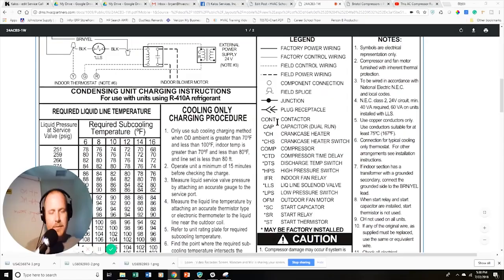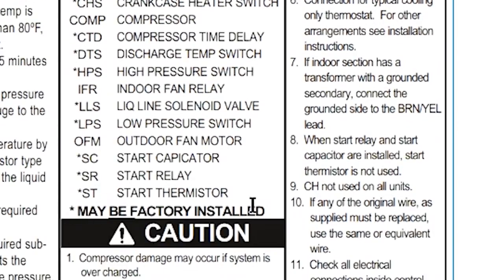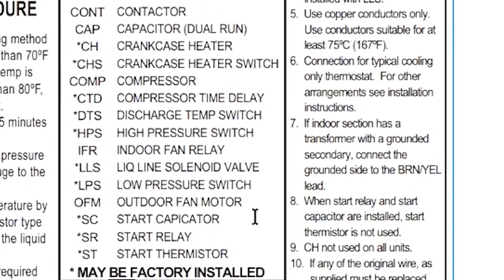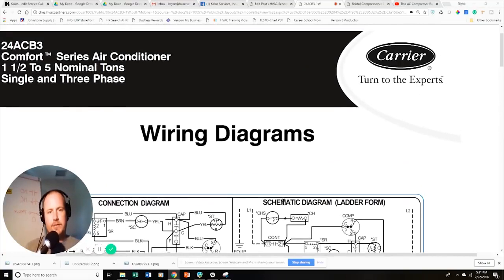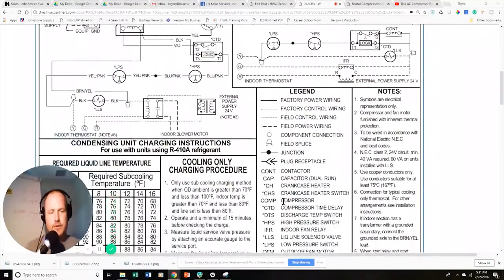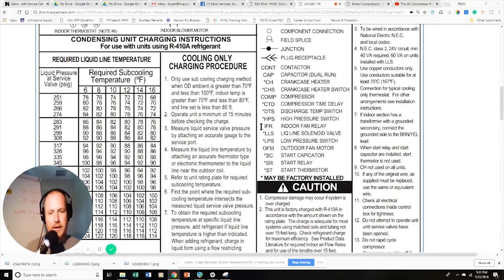The diagram has a bunch of nomenclature — abbreviations used. CONT is contactor, then capacitor, crankcase heater. A star means 'may be factory installed' — it may be there from the factory or it may not be. This is a universal diagram for a wide range of Carrier comfort series air conditioners, so crankcase heater, crankcase heater switch, compressor time delay, discharge temperature switch — those may or may not be present. High pressure switch and indoor fan relay will be there.